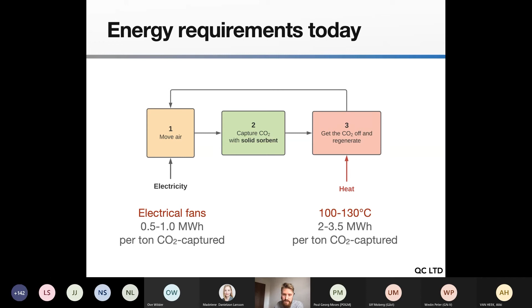The rough numbers are maybe 0.5 to 1 megawatt hour of electricity to move air, and 2 up to maybe even 5 megawatt hours of heat to regenerate the sorbent.